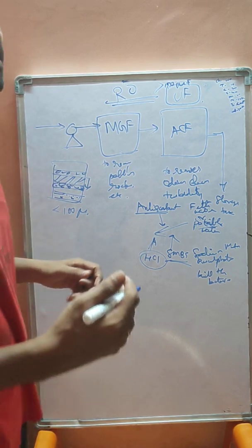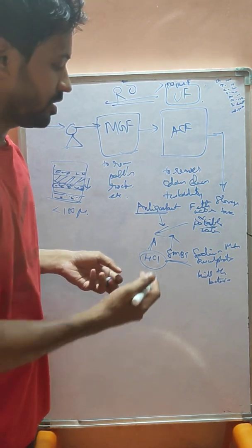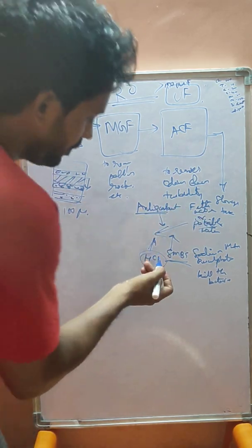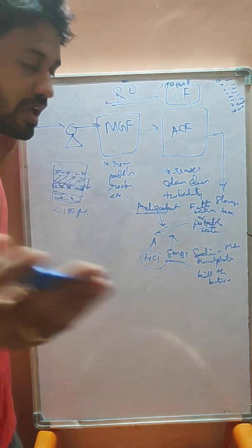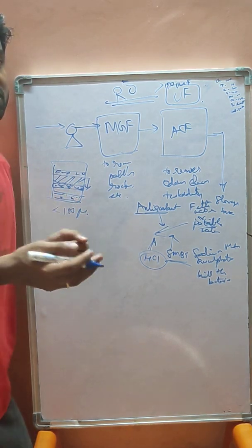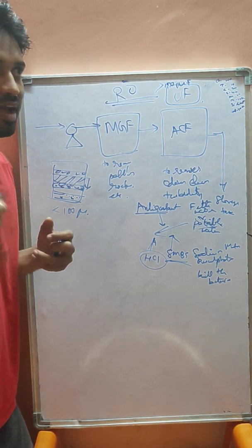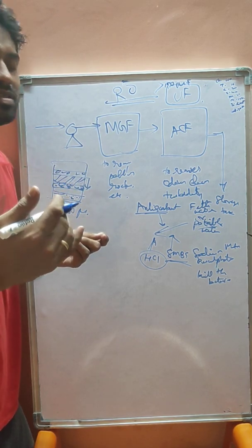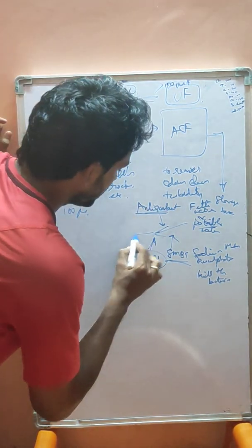If the water is more acidic, then we have to go for the addition of a basic component, such as caustic or ammonia. Sometimes ammonia can also be used for adjusting the pH. Mostly ammonia is used in plating shops where the pH has to be maintained because the baths are very acidic. When adding ammonia, we can easily get back to a neutral pH, around 6 to 8.5.